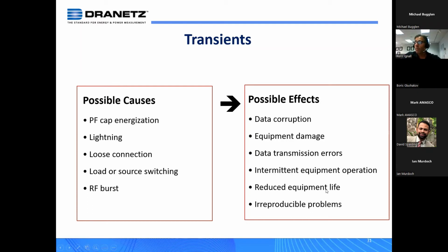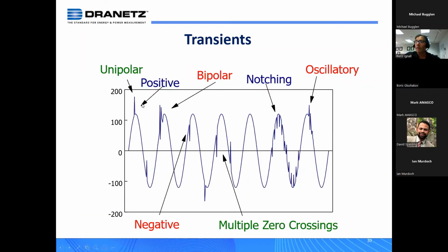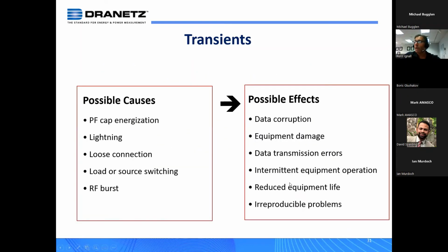And certainly repeated transients, mostly positive transients, can reduce the life of electronic components, power supplies, and things that are exposed to that. So you can kind of consider, we'll go back a slide, if a lot of positive transients are occurring, well, maybe it can weaken the front end or the power supply of these electronic components of whatever's there, whether it be for your circuitry, for your switch gear, or also the loads that are plugged in, the servers, the switches, and things like that. It can kind of reduce the life of electronic components and specifically their power supplies.